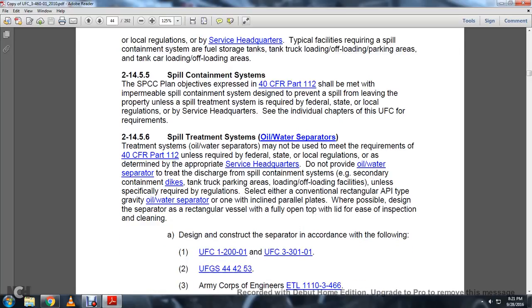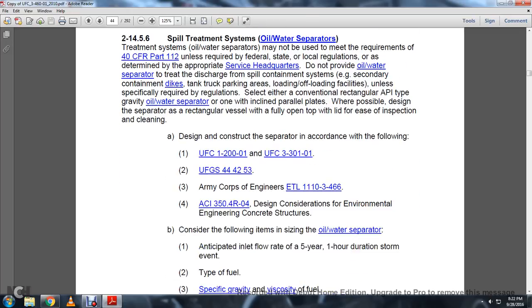214.5.6 Spill treatment and waste spill treatment systems or oil water separators. Treatment systems or oil water separators may not also be used to meet the requirements of 40 CFR Part 112 unless required by the federal, state, and local regulations or determined by an appropriate service headquarters. Do not provide oil water separators to treat discharge from spill containment systems, secondary containment dikes, tank truck parking areas, loading, offloading facilities unless specifically required by the regulations. Select either conventional or rectangular API gravity oil water separators or one of the inclined parallel plates. Whenever possible, design the separator as rectangular vessels with a fully open top and lid for ease of inspection and cleaning.